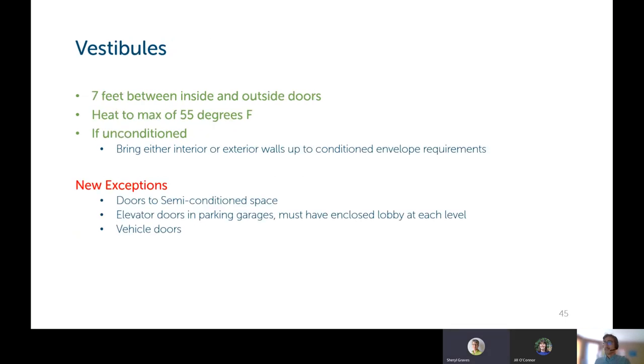Yeah, that makes sense. All right, the last slide I have for the envelope is vestibules. There needs to be 7 feet between the inside and outside doors of a vestibule. They need to be heated to a maximum of 55 degrees. I believe they cannot be cooled. And if they're unconditioned vestibules, not heated or cooled at all, you need to bring either the interior or exterior wall of that vestibule up to the envelope requirements of the energy code.